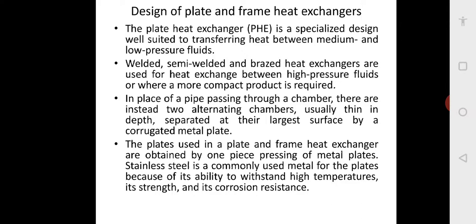The plates used in the plate and frame heat exchanger are obtained by one-piece pressing of metal plates. Stainless steel is a common metal used because of its ability to withstand high temperatures, its high strength, and corrosion resistance. Various grades of stainless steel are used — SS 304, 316, and others.